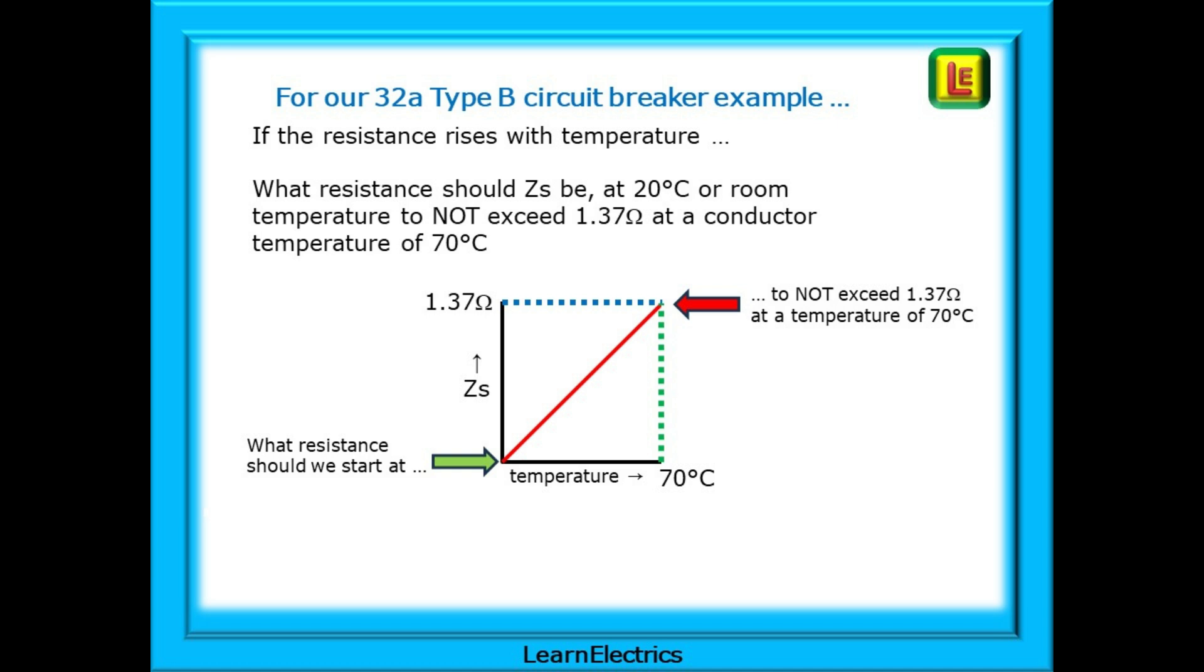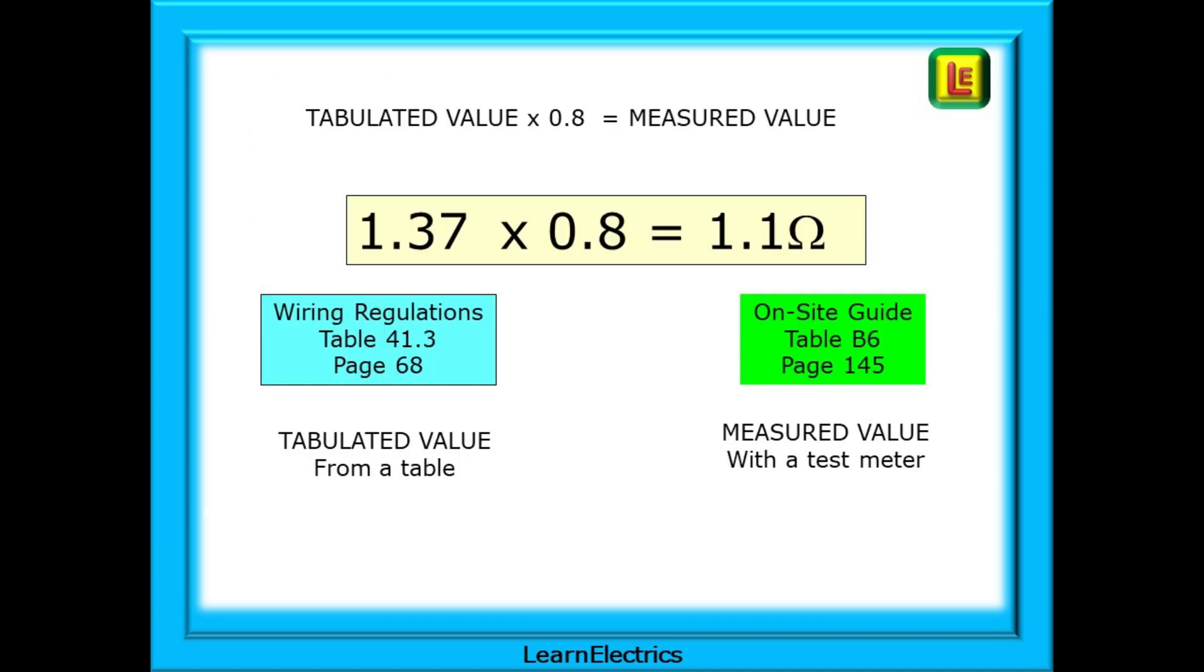So if the resistance rises with temperature what resistance should ZS be at 20 degrees centigrade or room temperature to not exceed 1.37 ohms at the conductor temperature of 70 degrees Celsius. What is the new starting point? How much lower must the resistance be? On this drawing what should the starting point be at the green arrow at 20 degrees so that we do not exceed 1.37 ohms at the red arrow when the conductor is at 70 degrees? This is where the 80% rule comes in. Take the tabulated value and multiply by 0.8 to get yet another value.